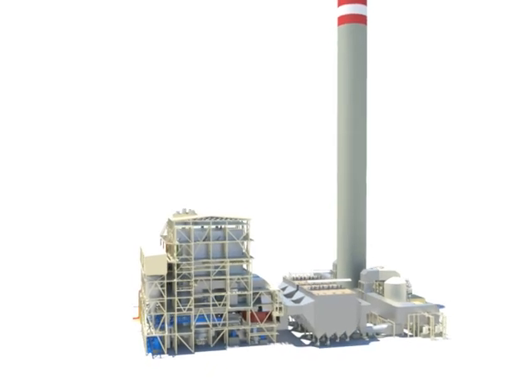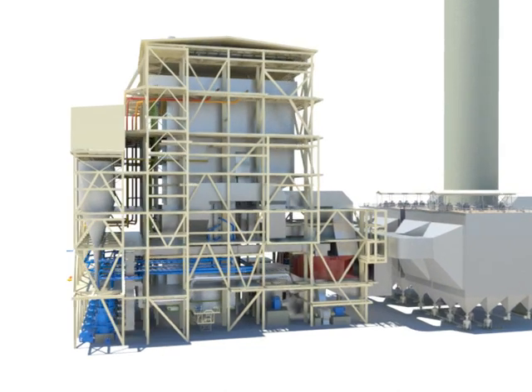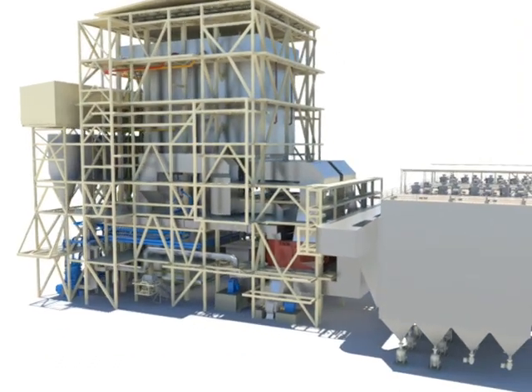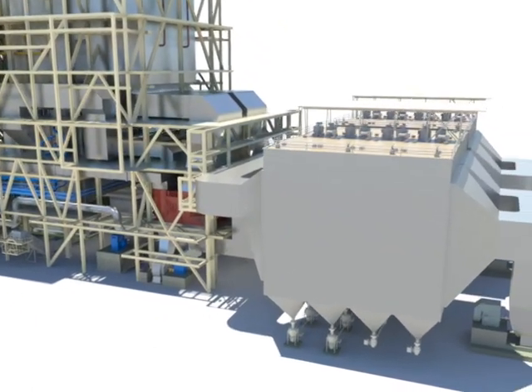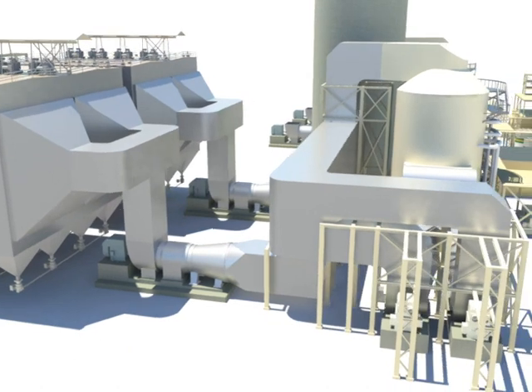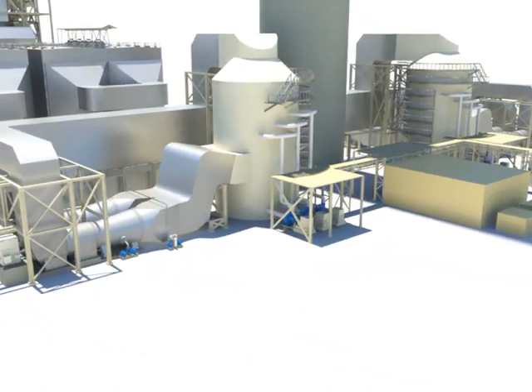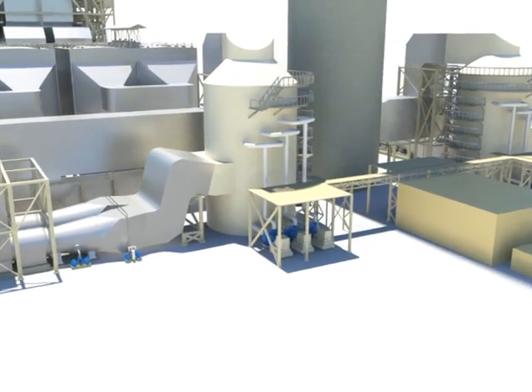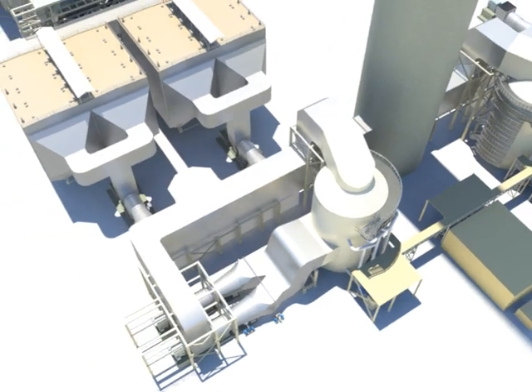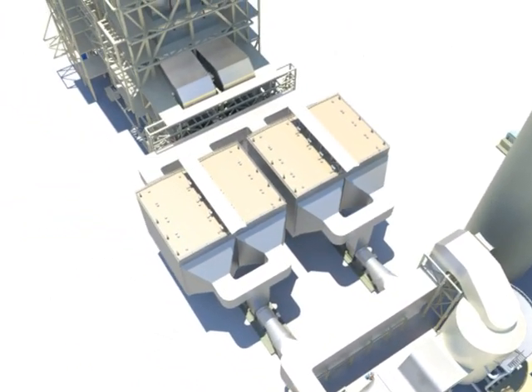The draft system is equipment which supplies appropriately preheated combustion air and primary air heated by the air preheater to the boiler, and emits the formed combustion gas to the atmosphere through the chimney. The system consists of the forced draft system, burned gas exhaust-induced draft fan system, pulverized coal drying transfer system, flame-detector cooling air system, and pulverizer-seal air system.